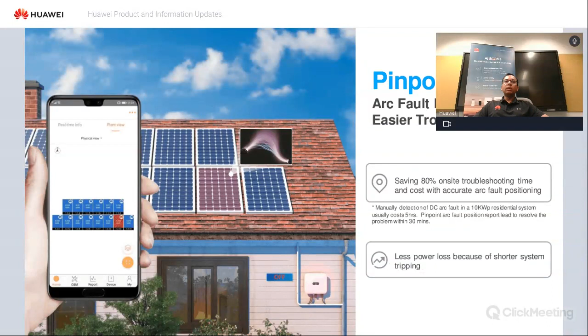Just pressing on the arc fault. So we all know what an arc fault is. Unreliable soldered joints or broken cables or any loose PV connectors can cause arc faults. And the AFCI, the arc fault circuit interrupter, is a proprietary algorithm that Huawei inverters have, and it's on by default in most of our inverters. And there are third-party studies, white papers and independent studies that I'm more than happy to share. I can talk about just AFCI for hours. I won't, but I can because I'm just so passionate about the safety and reliability.